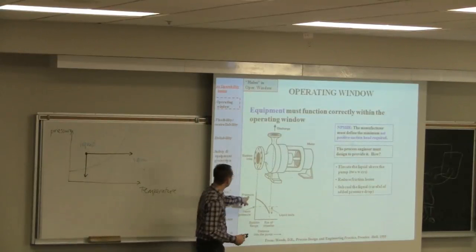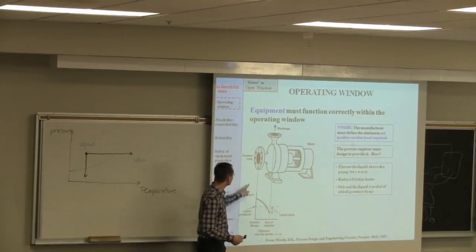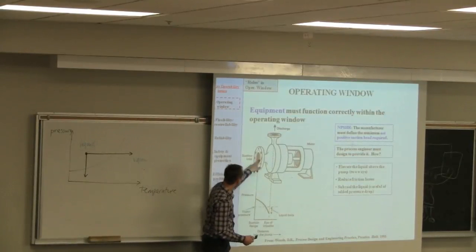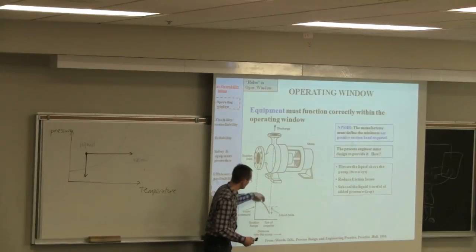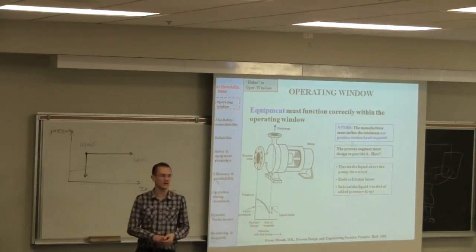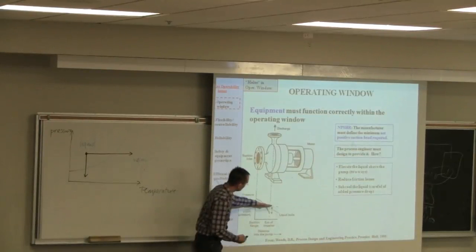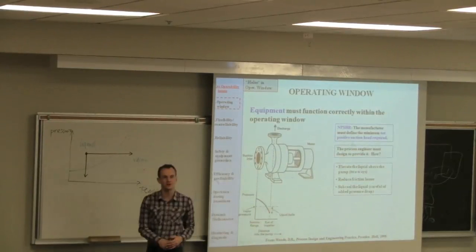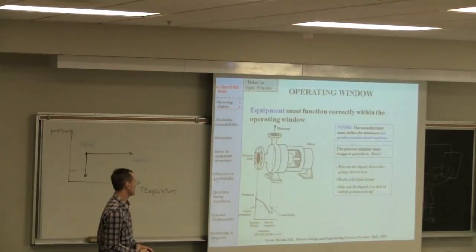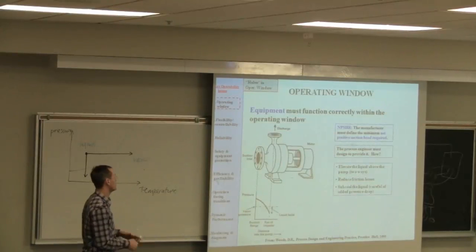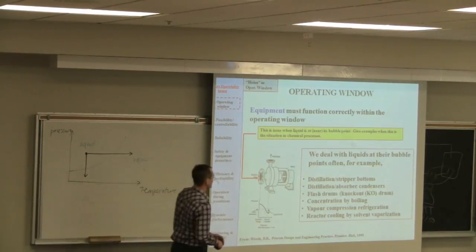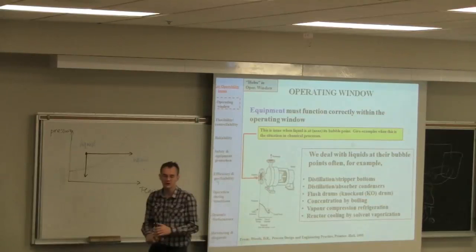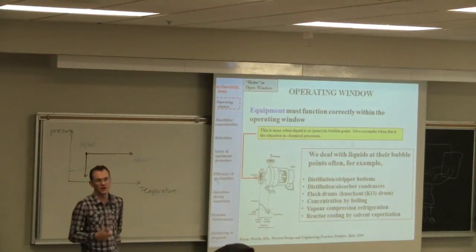Here's a plot that I was looking for earlier. The profile of the pressure through the pump, as the fluid comes from the inlet side, whereas high pressure, there's a substantial drop. Well, there's somewhat of a drop through that flange. But then also, as you enter the eye of the pump, there's almost, this curve doesn't show, but it's almost a more vertical drop as that fluid suddenly gets accelerated into higher velocities. The risk is that if your vapor pressure is over here, and you drop below the pressure, you get boiling in the vanes of the pump, which is the cavitation. And that sound will be created from the bubbles, the vapor being created, and then popping as the pressure increases again on the output. I'll post this online, and you can get this down for a minute. Essentially, there's so many of our unit operations that operate close to boiling point that this is an important issue, which is why we give it so much attention.